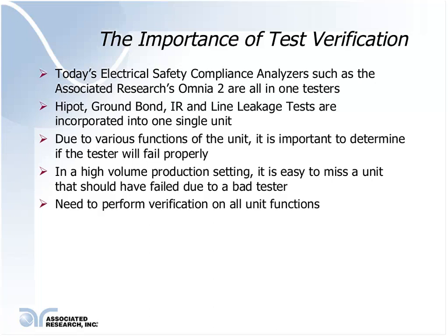So therefore, performing verification on all unit functions ensures that a test unit is operating within the specified parameters. And also, according to UL procedures, if the test unit is taking measurements to make a determination on electrical safety, then it must be verified.